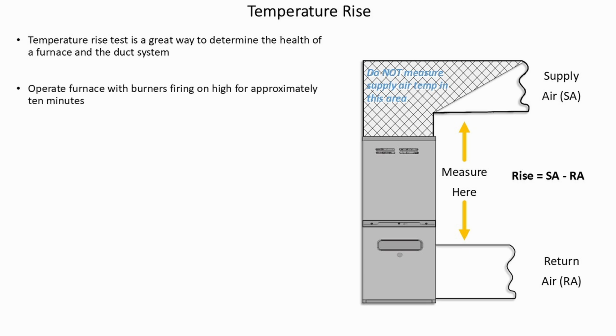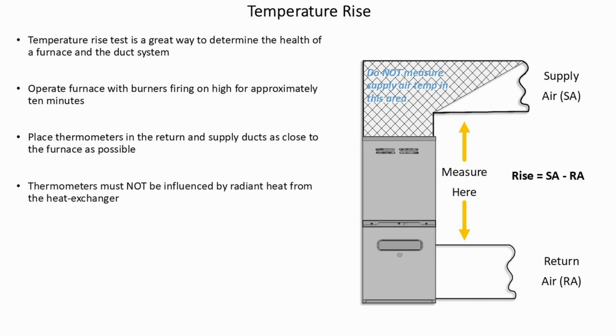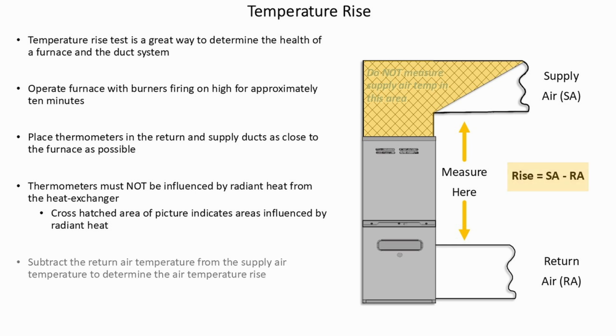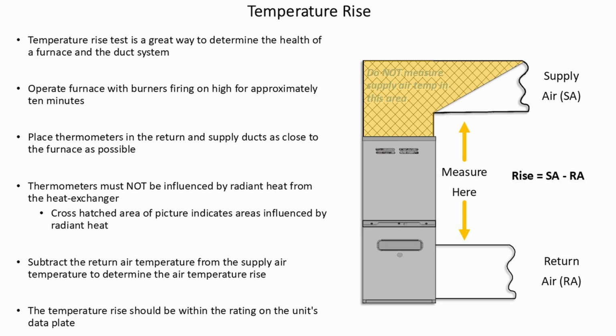Operate the furnace with the burners firing on high for approximately 10 minutes. Place thermometers in the return air and the supply air ducts as close to the furnace as possible. Thermometers must not be influenced by radiant heat from the heat exchanger. The cross-hatched area in the picture indicates areas that are influenced by radiant heat. Subtract the return air temperature from the supply air temperature to determine a temperature rise. The temperature rise should be within the rating on the unit's data plate.